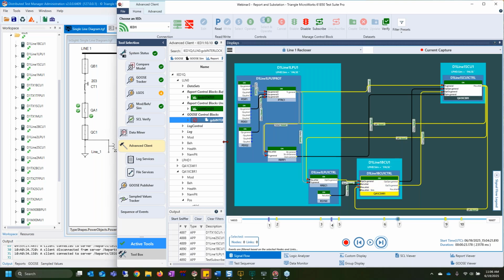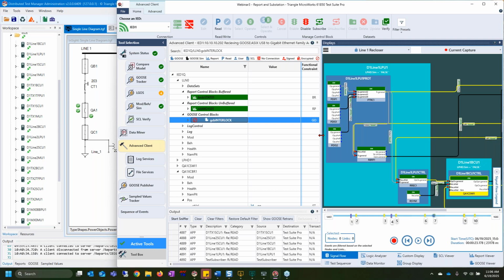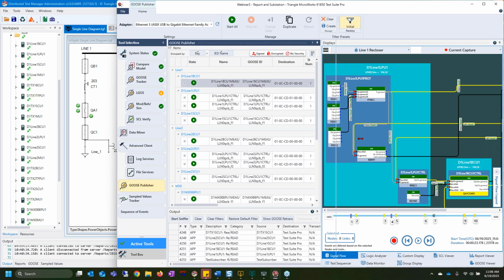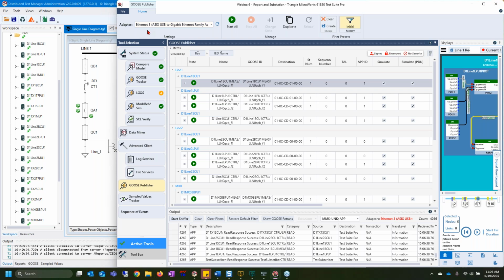And the other tool I was going to mention for TSP is our GOOSE Publisher. Occasionally, you might need to issue a GOOSE message, potentially without a server. This can be used to replace missing hardware, to set up initial conditions for test environments where you don't have the ability to make physical changes to your hardware, or potentially to set up virtual isolation. So if you go to the GOOSE Publisher here, similar to the GOOSE Tracker, you would select an adapter where you'd want to publish this GOOSE on. Since TSP knows all of the GOOSE streams that you need for your system, we've been able to supply these and break them down by bay.